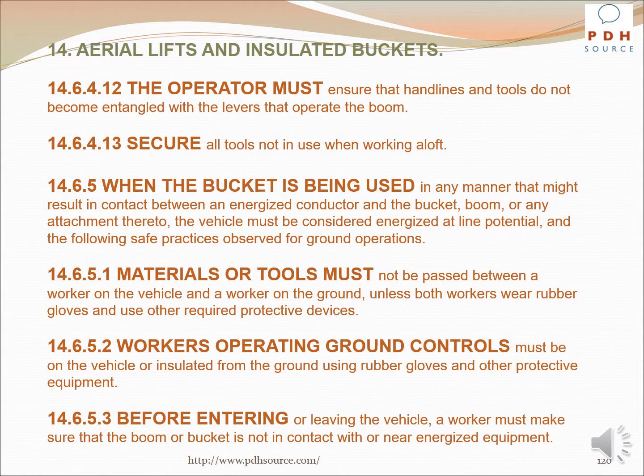When the bucket is being used in any manner that might result in contact between an energized conductor and the bucket, boom, or any attachment thereto, the vehicle must be considered energized at line potential and the following safe practices observed for ground operation. Materials or tools must not be passed between a worker on the vehicle and a worker on the ground unless both workers wear rubber gloves and use other required protective devices. Workers operating ground controls must be on the vehicle or insulated from the ground using rubber gloves and other protective equipment. Before entering or leaving the vehicle, a worker must make sure that the boom or bucket is not in contact with or near energized equipment.